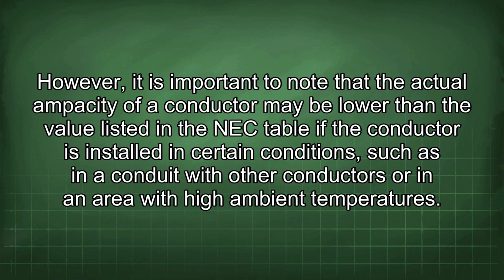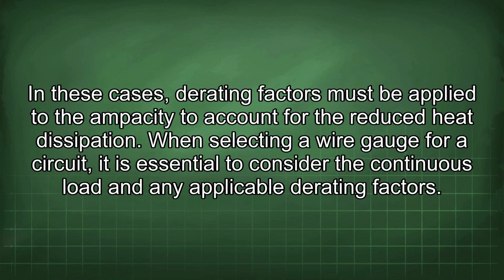However, it is important to note that the actual ampacity of a conductor may be lower than the value listed in the NEC table if the conductor is installed in certain conditions, such as in a conduit with other conductors or in an area with high ambient temperatures. In these cases, derating factors must be applied to the ampacity to account for the reduced heat dissipation.